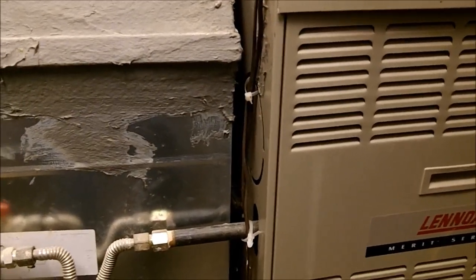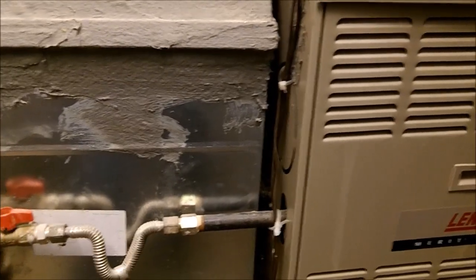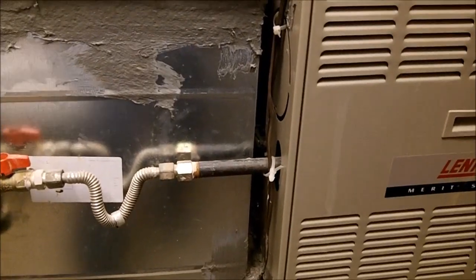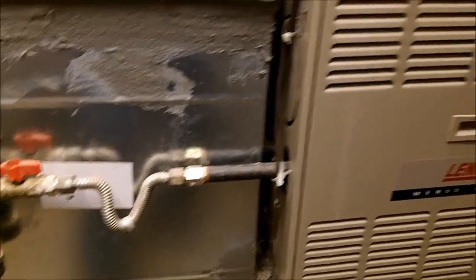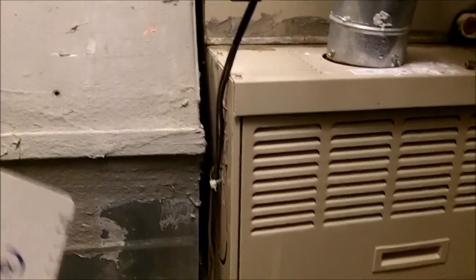So he asked me about a filter rack. Well, I was going to tell him that hey man, you really need to put a filter in, some way to hold the filter in. And then I got to notice the 16 by 20 hole instead of the 16 by 25. So in order to make up for this system not working properly, somebody added something.